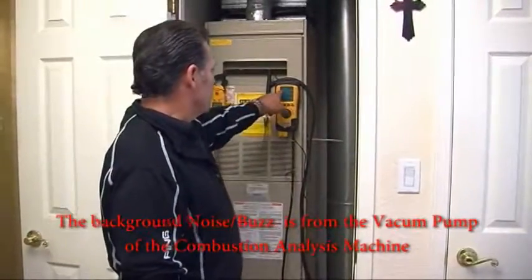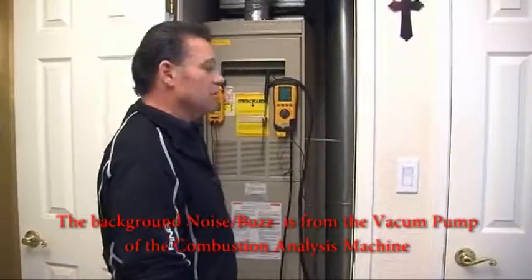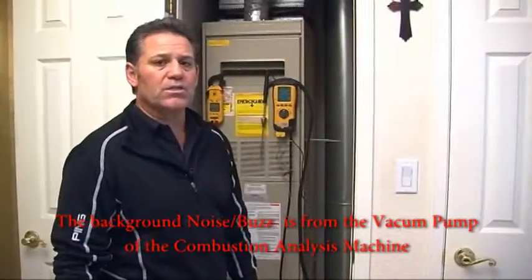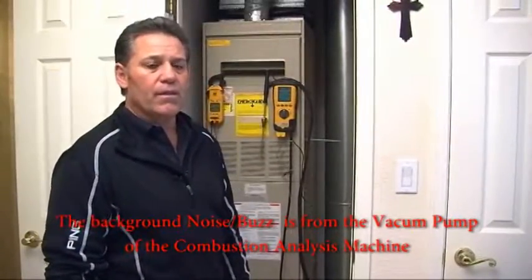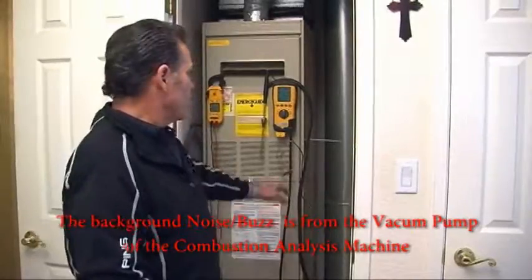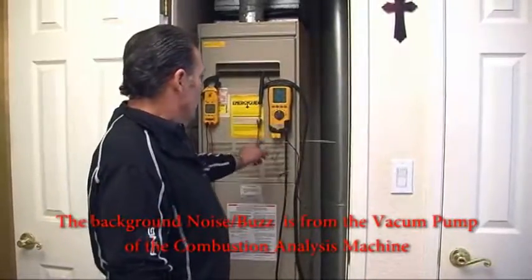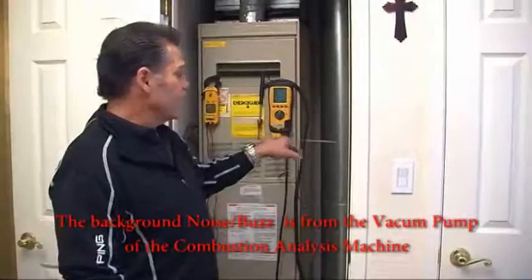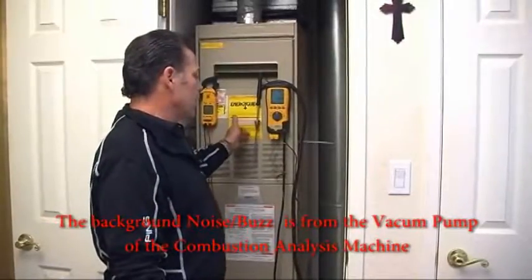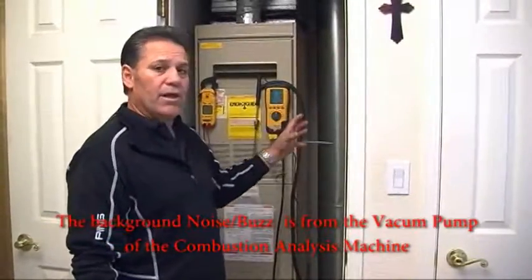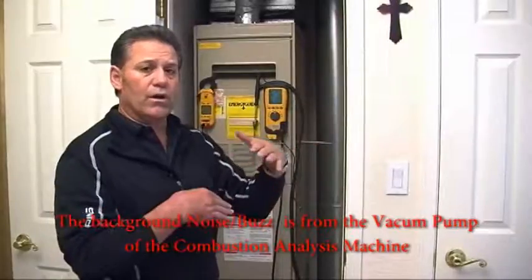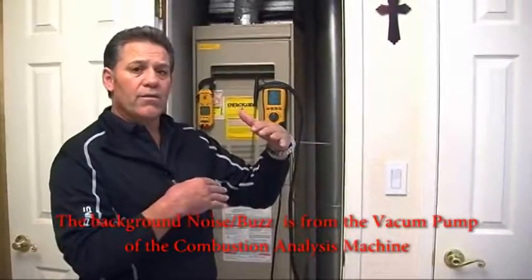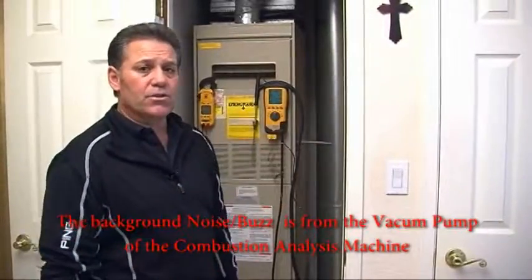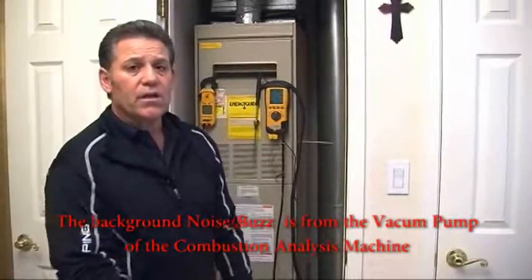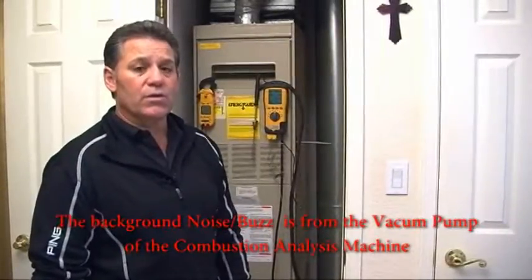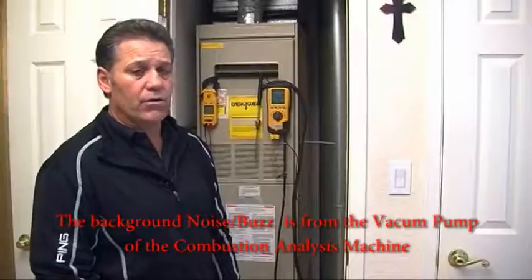But as you see, when you turn it on, the oxygen's at 20.9. That's the free oxygen in the air everywhere. So that's when you know your machine is calibrated. What I'm going to do right now is a temperature rise. On the inside of this panel, there's a metal plate where the manufacturer gives you all of the recommendations of where they want the parameters to be. On the temperature rise for this furnace, the temperature rises between 70 and 100 degrees.